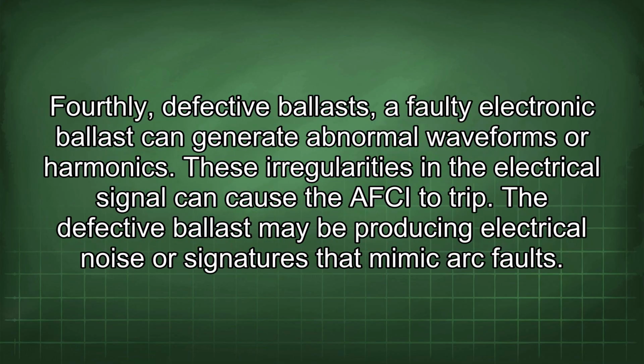Fourthly, defective or faulty electronic ballasts can generate abnormal waveforms or harmonics. These irregularities in the electrical signal can cause the AFCI to trip. The defective ballast may be producing electrical noise or signatures that mimic arc faults.